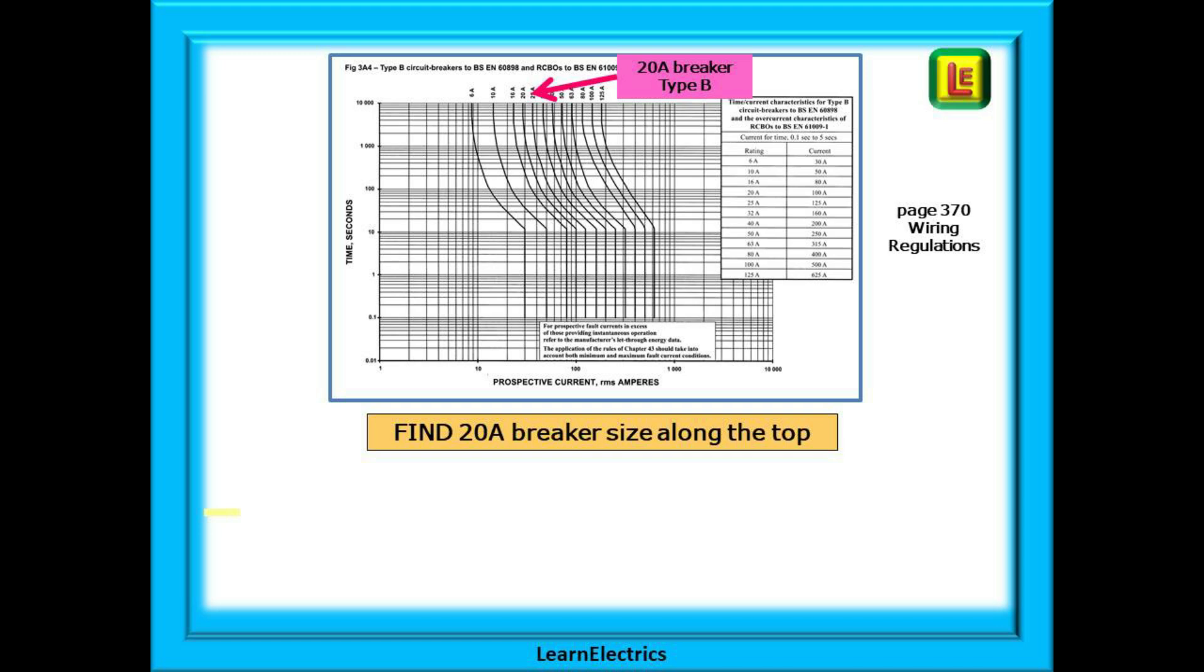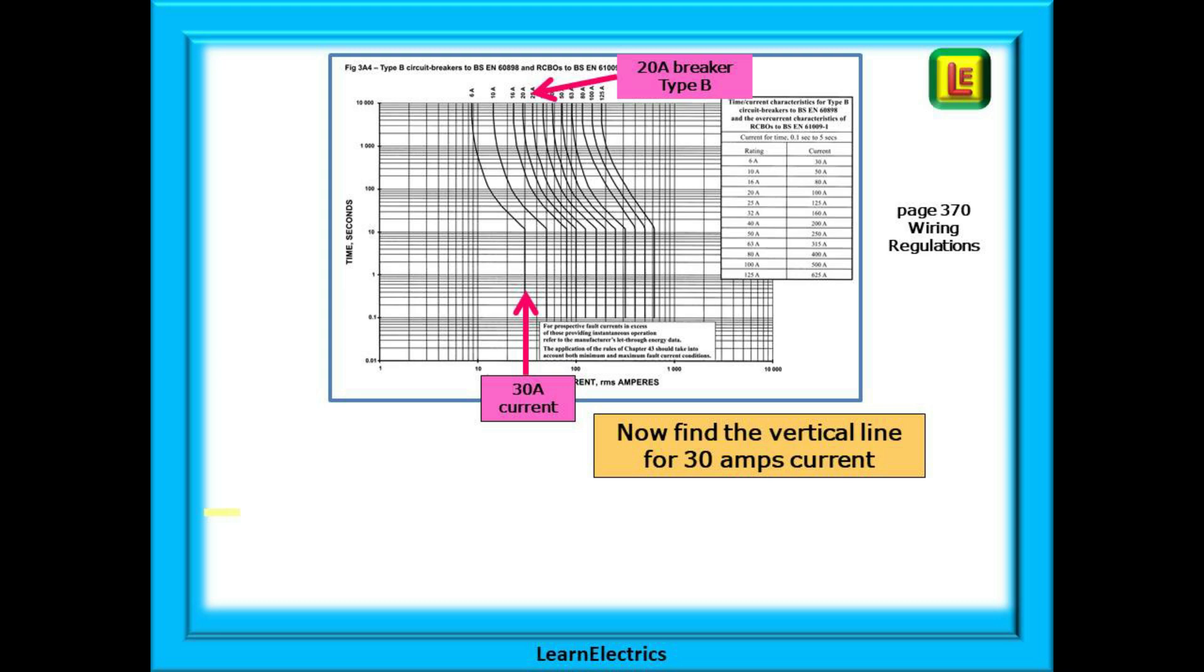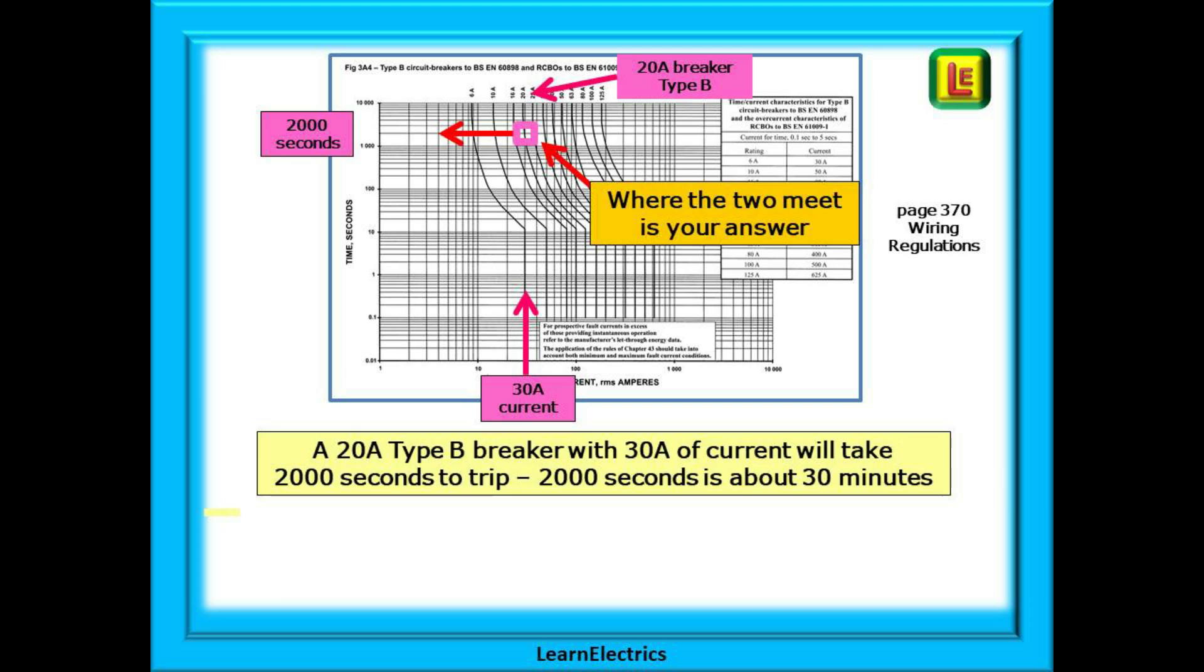First, find the response curve for a 20 amp breaker along the top. Now find the vertical line for 30 amps along the bottom. Follow this 30 amp line upwards until it crosses the curved line for a 20 amp breaker. Where the two lines meet, there is your answer.